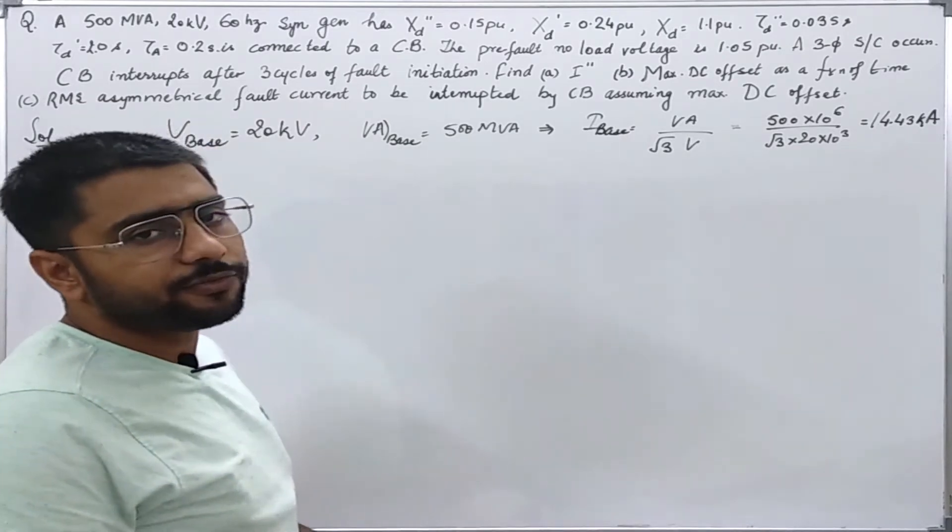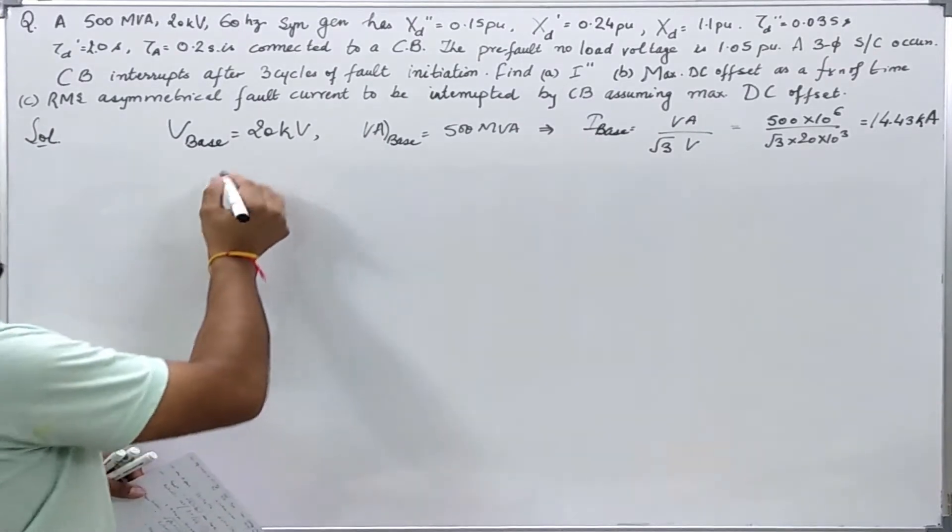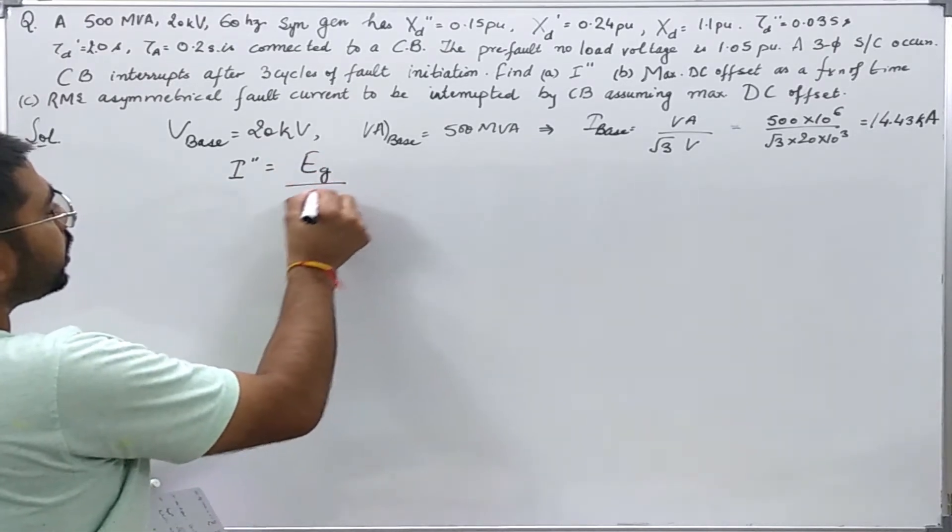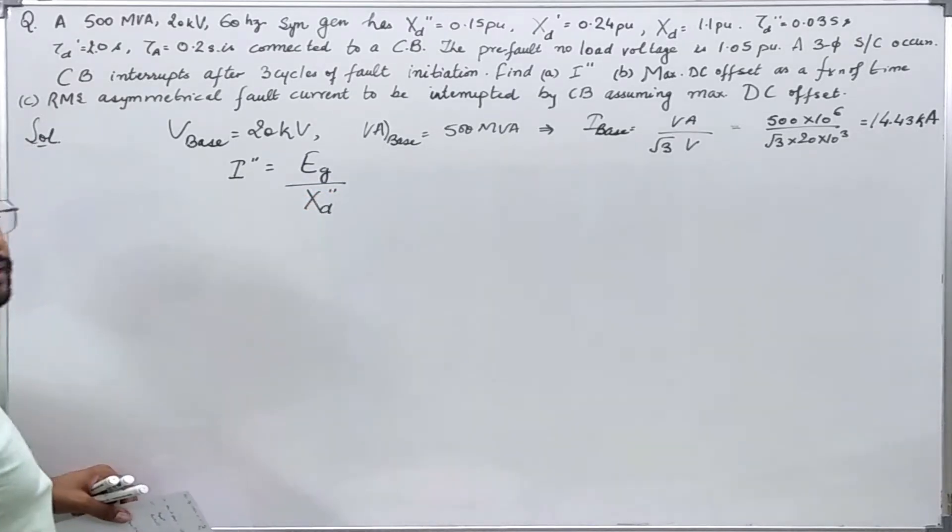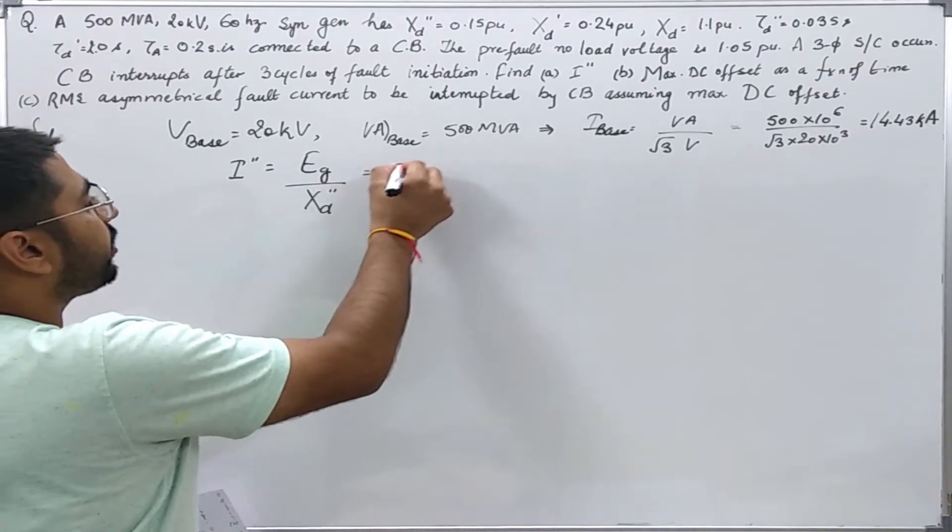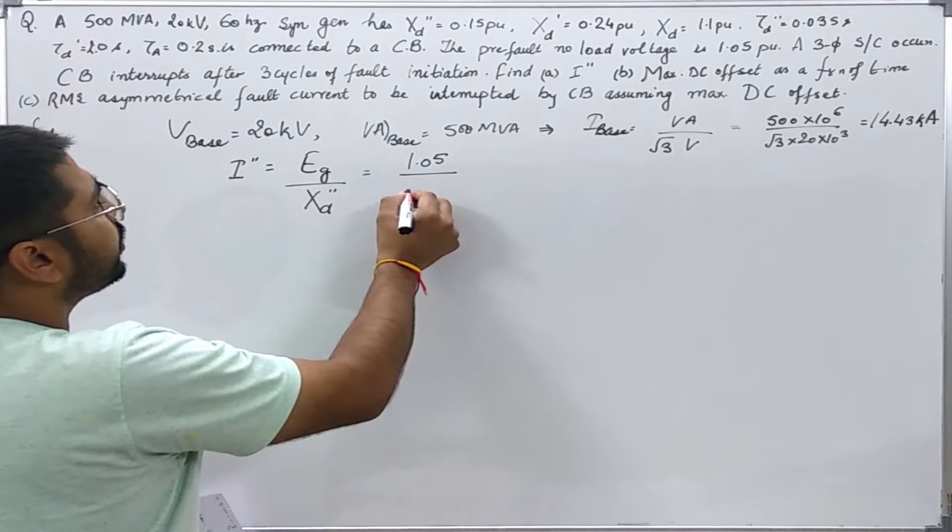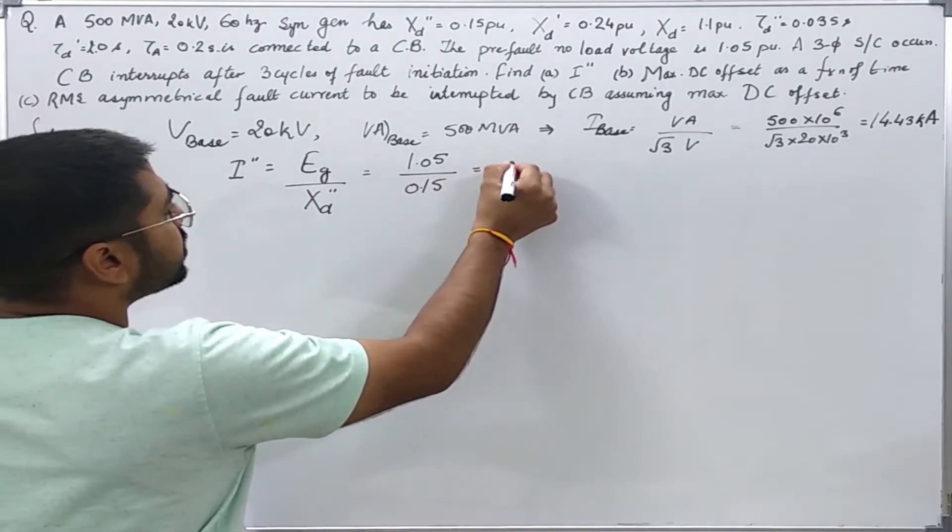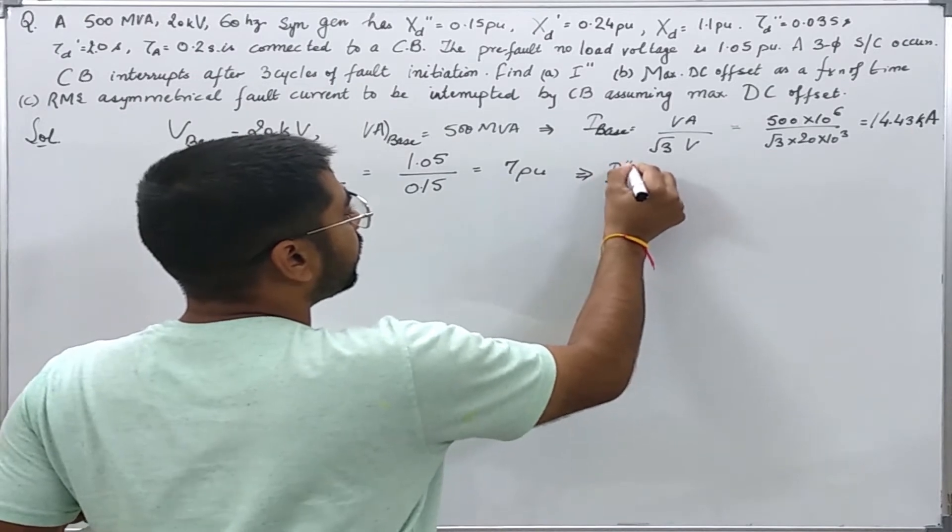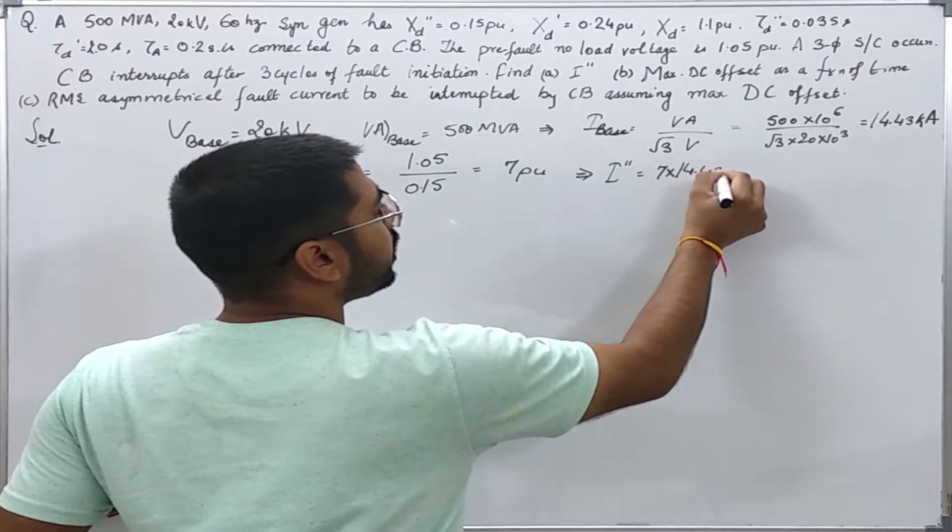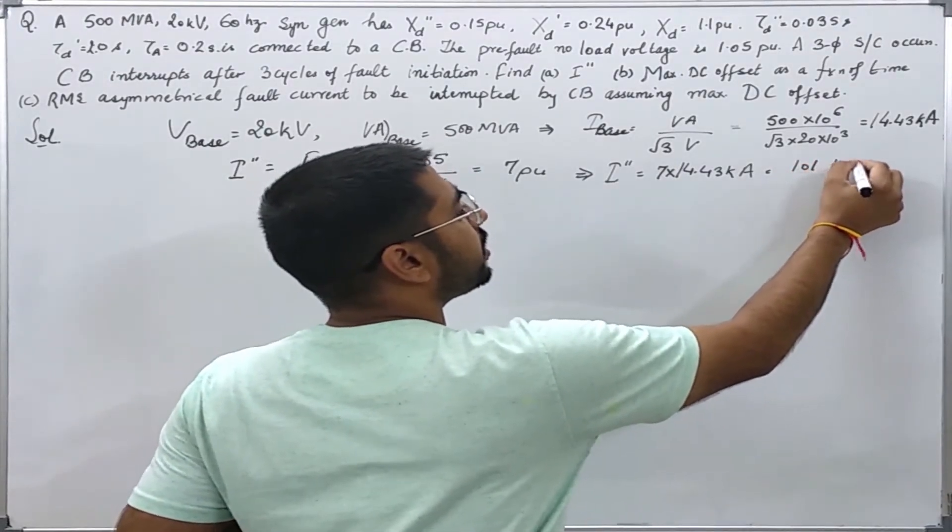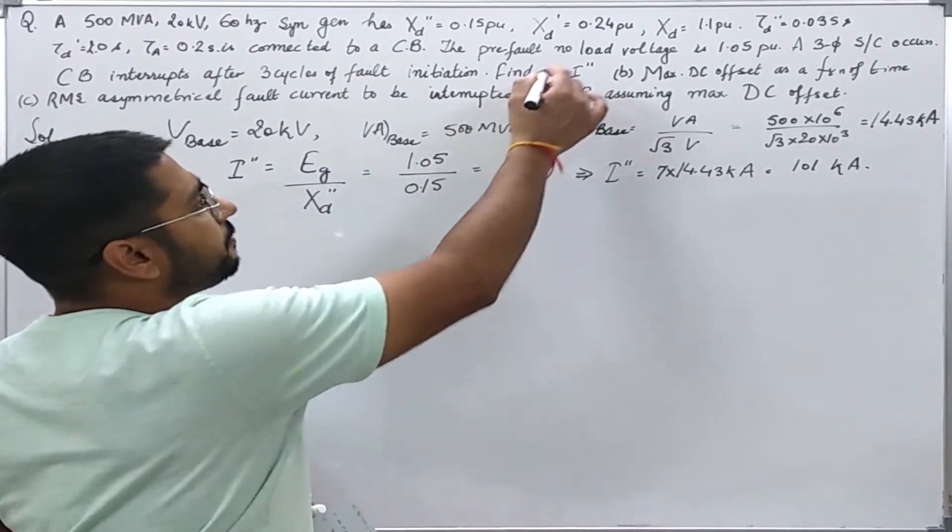I have found the base current now. I will find the sub-transient fault current. From the definition of sub-transient fault current, it is nothing but the ratio of voltage to the sub-transient reactance. We are just dealing with the magnitudes, so I have not written j here showing that it is a reactance. It will come out as 1.05 divided by 0.15 and it is equal to 7 per unit, which implies that in amps it comes out to be 7 into I base which is 14.43 kilo amps, and on multiplication it comes out to be 101 kilo ampere. This solves the first part.